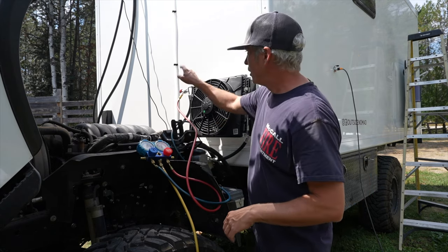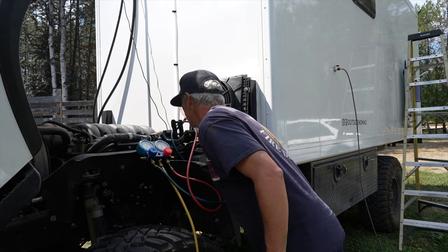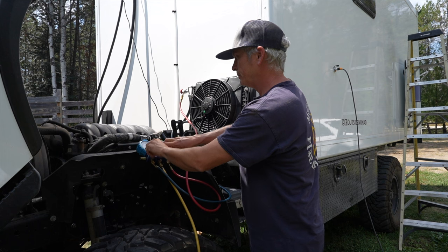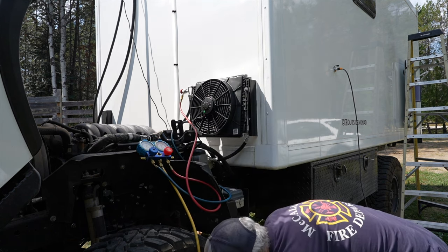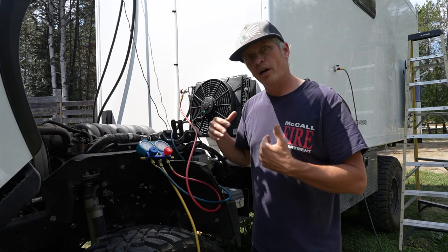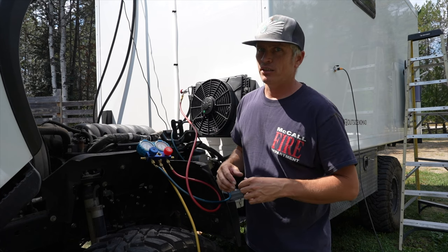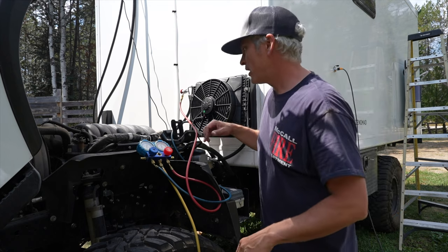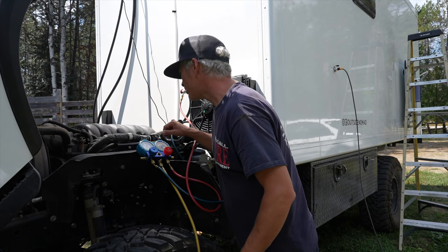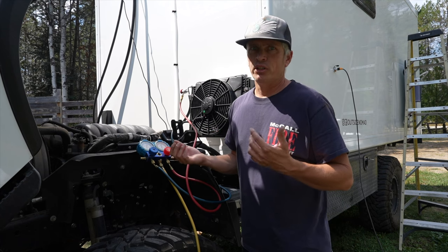Now we can open up the valves on the high and low connection by threading that knob in, and then open up the two valves on our pressure gauges. Now we've turned on the pump — everything's open and the pump is drawing out a vacuum, which should also be pulling out moisture that's really bad for the system, getting it prepped for the refrigerant. I'm pulling about negative 25 inches of mercury on the vacuum, which is pretty good for the altitude I'm at.